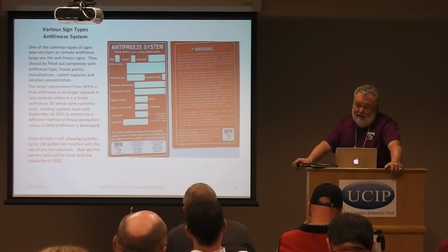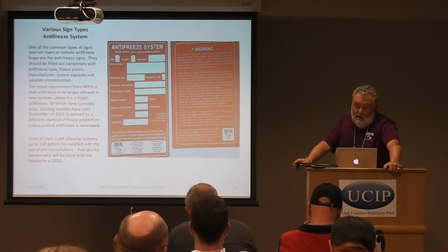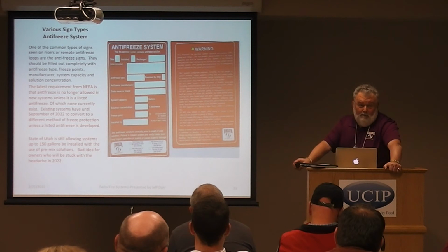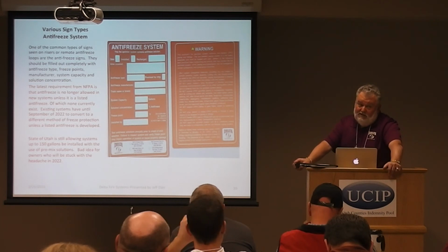And because of that, when these go off, there's potential for, like I say, Truckee, California, there was one person died. Out here in Harriman, there was a fire at the Farm Gate Apartments. Mother and her young son were playing with matches, the head right above him went off, and from what I understand, they were burned, and one fireman told me, he says, the best I can equate to that is I was in Vietnam and it looked like napalm. He says, so, NFPA now says any new systems, you cannot use antifreeze unless it's with an approved solution. Currently there is none, doesn't look like there will be any.